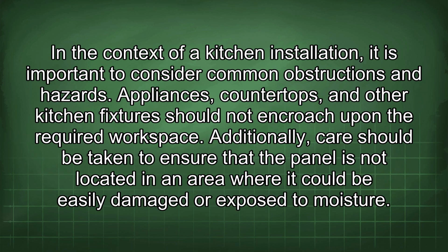In the context of a kitchen installation, it is important to consider common obstructions and hazards. Appliances, countertops, and other kitchen fixtures should not encroach upon the required workspace. Additionally, care should be taken to ensure that the panel is not located in an area where it could be easily damaged or exposed to moisture.